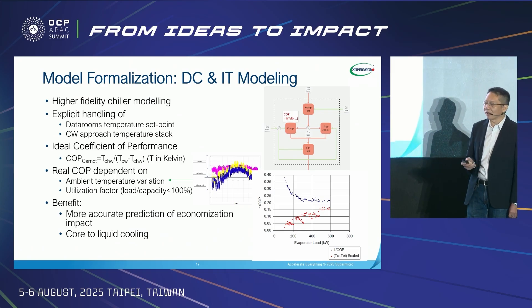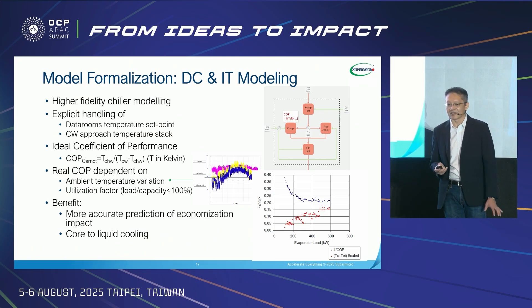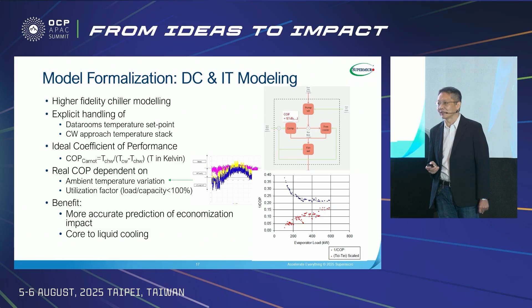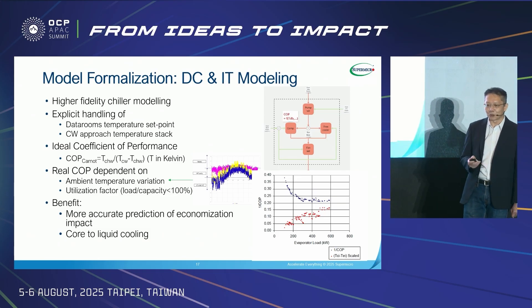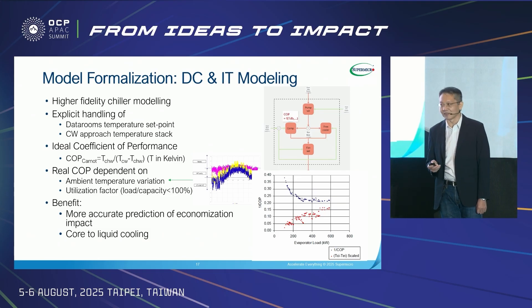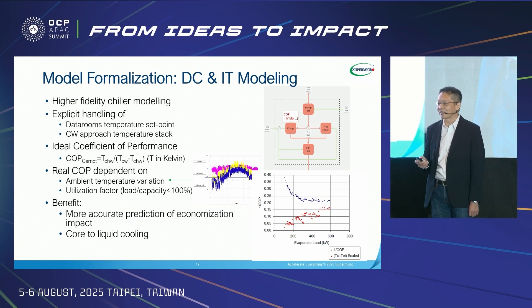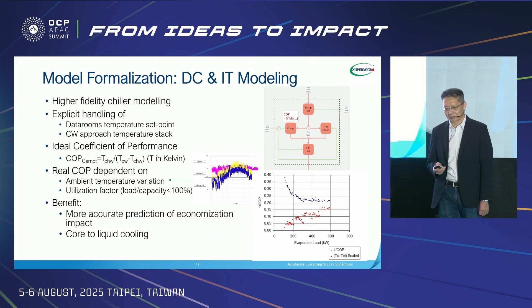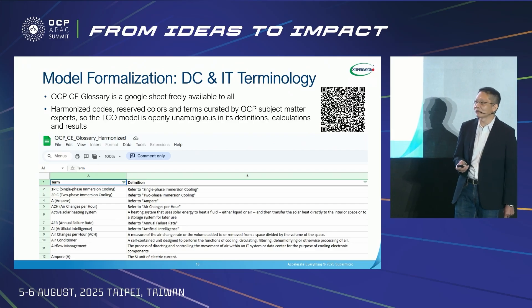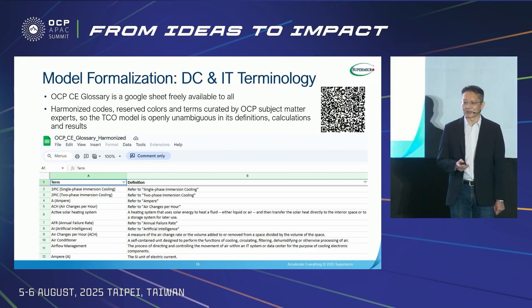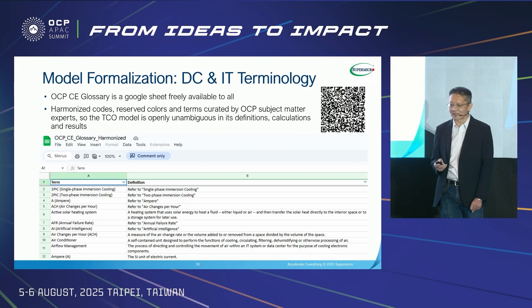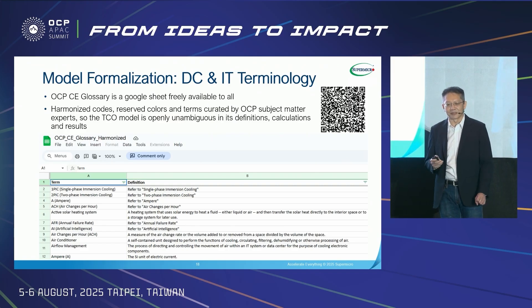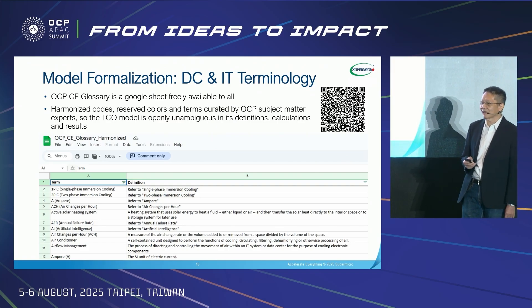It is recognized that among all four mechanical energy consumers — compressors, pumps, fans, and heat rejection units — compressor energy accounts for the largest ratio of overall mechanical energy. So it makes sense to have an elaborated chiller energy calculation with dynamic COP, which is subject to climate data and the data room set point temperatures. This QR code links to the OCP Cooling Environment Workgroup harmonized codes, reserved colors, and terms curated by OCP subject matter experts, so the TCO model is openly unambiguous in its definitions, calculations, and results.